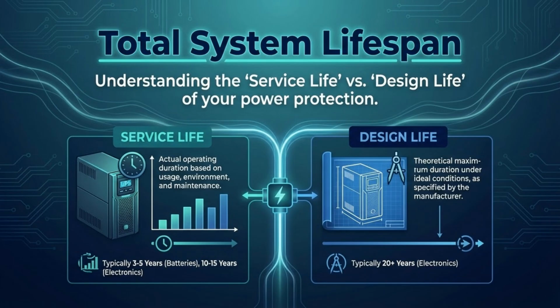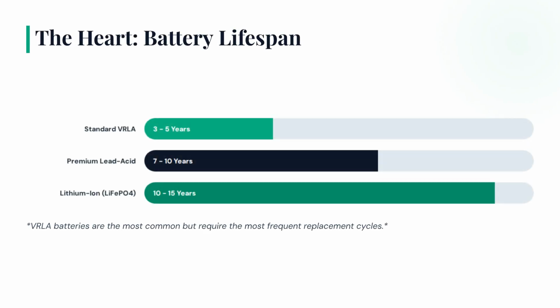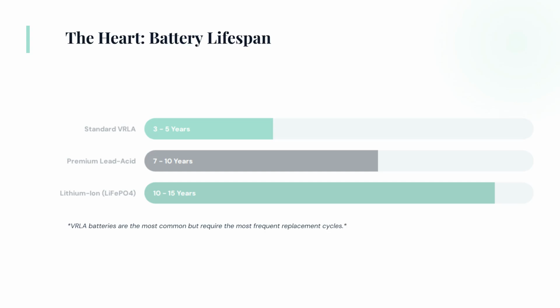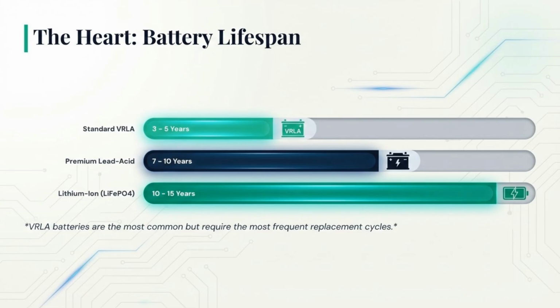Service life is the actual duration of operation, typically 3 to 5 years for batteries and 10 to 15 years for electronics. Design life is the theoretical maximum duration under ideal conditions, which can be 20 plus years for the electronics. The heart of the UPS is the battery. Standard VRLA batteries last 3 to 5 years, premium lead acid 7 to 10 years, and lithium-ion, or LiFePO4, can last 10 to 15 years. VRLA batteries require the most frequent replacement. As you can see, choosing the right battery chemistry significantly impacts the necessary replacement cycle and overall system dependability.